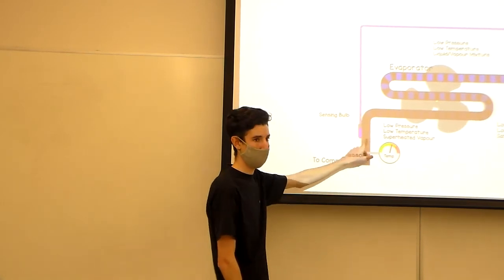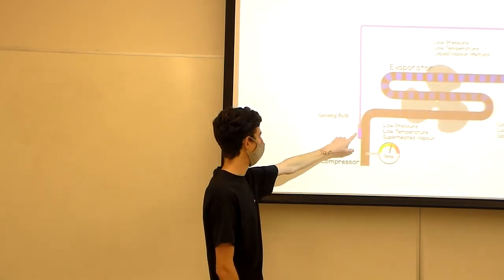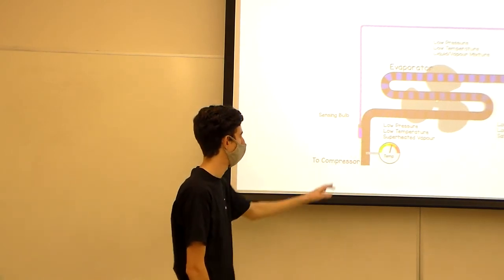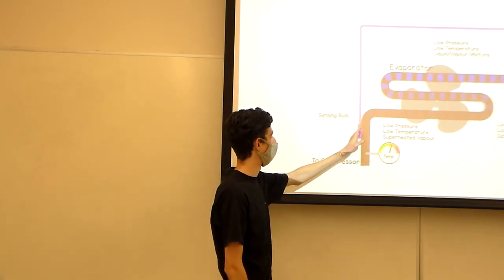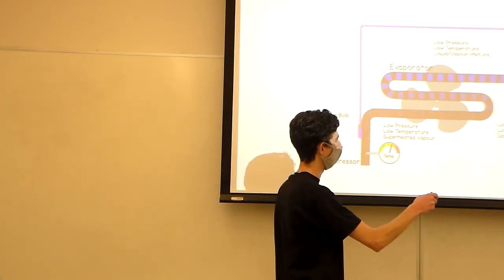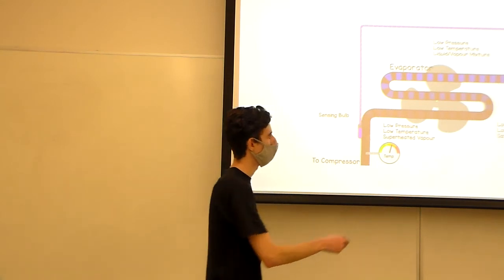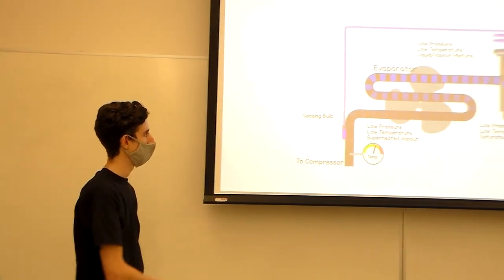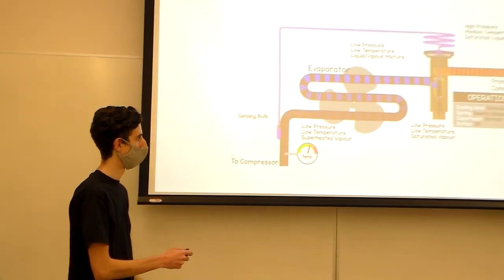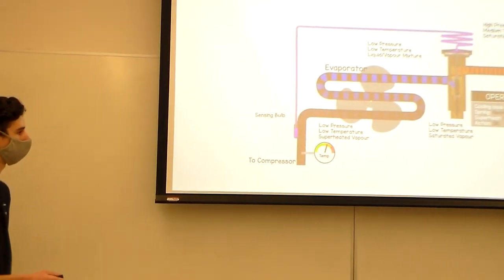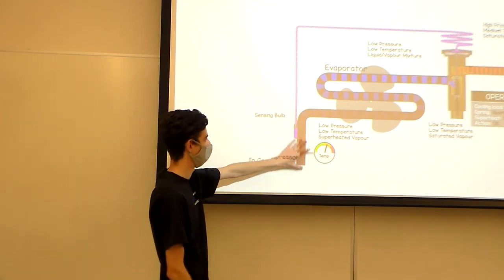And so depending on the temperature in this tube, this liquid inside, which is kind of like a separate, closed system, will heat up and vaporize. And then the more fluid we have pushing on that diaphragm, working against the pin, it'll push that pin down and allow for more liquid to pass through if the temperature is too high. So it kind of works to regulate the temperature and try to keep it consistent when it's coming out over here.